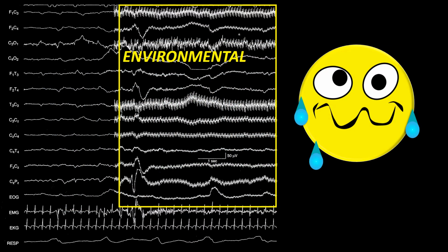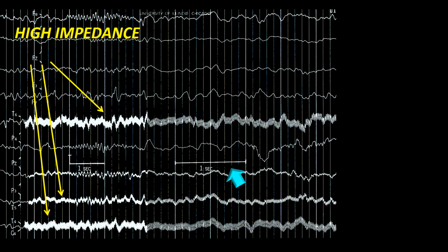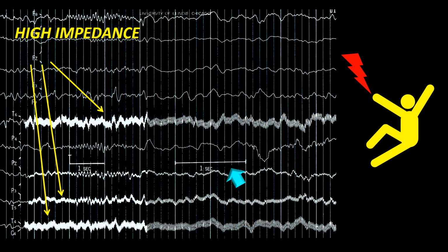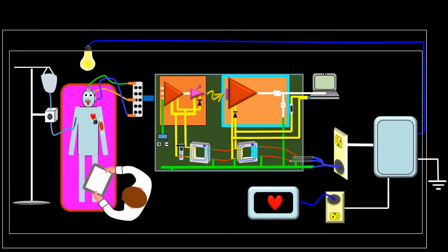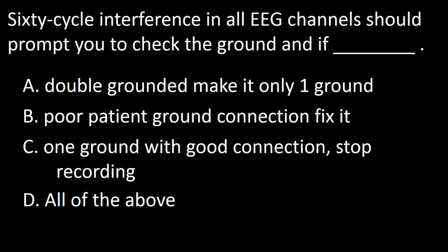If, while running an EEG, you find 60 Hz artifact in all channels or at least in multiple channels, you may confirm it by slowing down the recordings so as you can see each individual wave better and count them corresponding to 1 second. If it continues, then that indicates the possibility of health hazard. So the best thing to do is to take the electrodes off the patient. So the answer to this question is D.